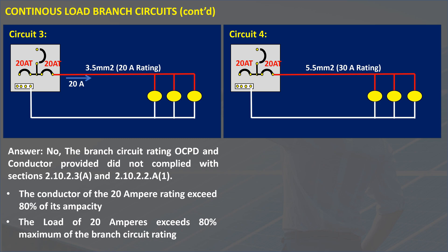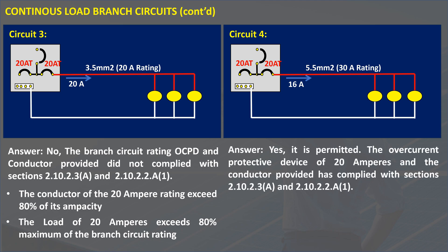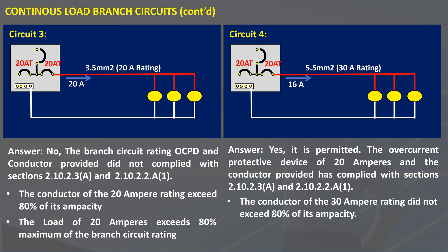Next is circuit 4. A 16 amperes continuous load is connected to a circuit rated at 20 amperes. The conductor provided is rated at 30 amperes, as shown. Is this circuit compliant with the code? Yes, it is permitted. The overcurrent protective device of 20 amperes and the conductor provided has complied with Sections 2.10.2.3 A and 2.10.2.2 A1. The conductor of the 30 amperes rating did not exceed 80% of its ampacity, and the rating of the circuit is 20 amperes, not 30 amperes. However, this circuit must only be loaded by 16 amperes maximum.